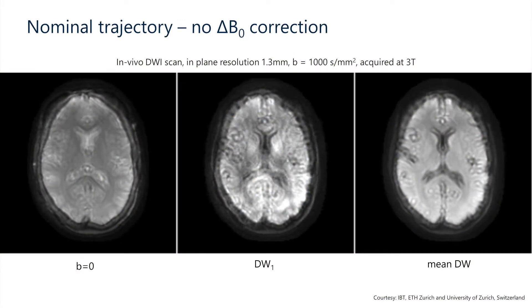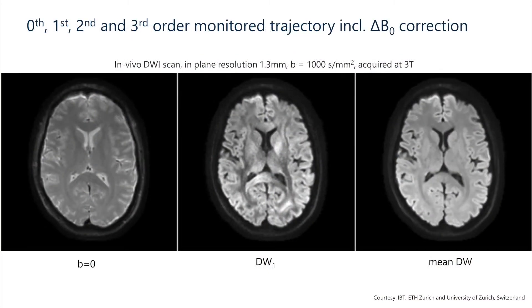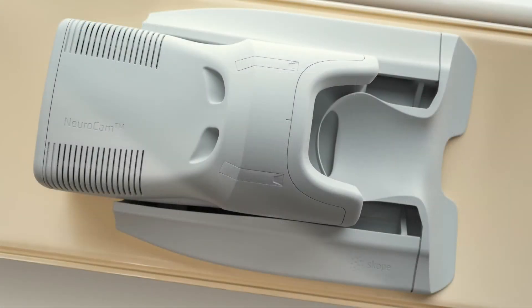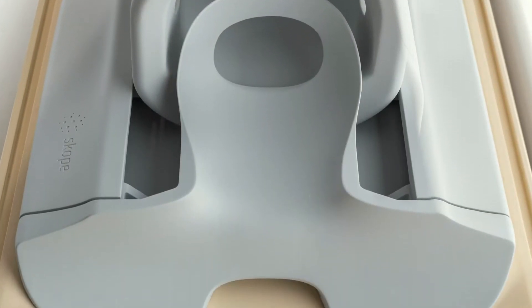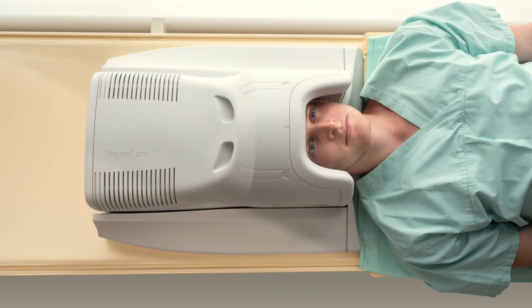Monitoring MRI field dynamics during MRI acquisition gives you the tool to reconstruct the most accurate and consistent diffusion-weighted data. The NeuroCam is our unique brain coil optimised for neuroscience research with incorporated spatiotemporal magnetic field monitoring capabilities for a single ready-to-use package for in vivo neuroimaging at 3T.